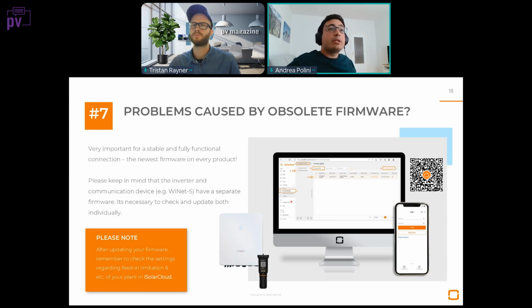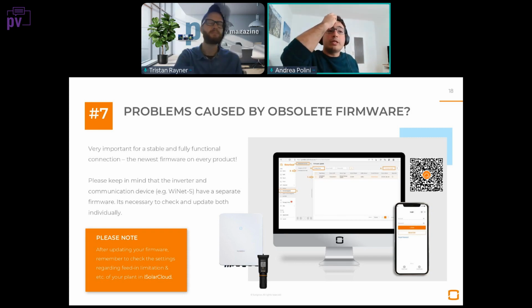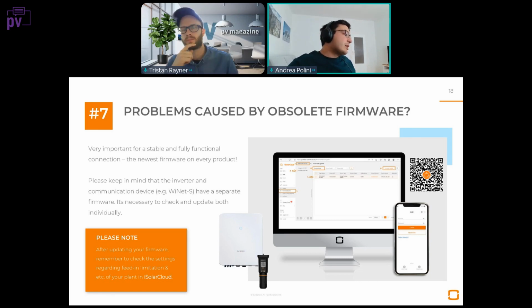And very important is to select, number one, the inverter, and to do the firmware update. And also from the drop-down menu, you can see at number 4 here, you need to select the communication module, so the WiNet dongle, to be updated to the latest version. This is quite important for the whole system to be updated. In the future, we are also adding the battery in the hybrid inverter plus battery combo as a separate item.